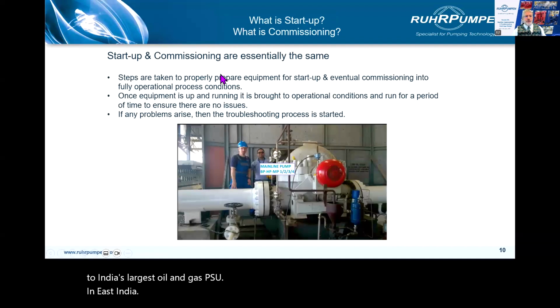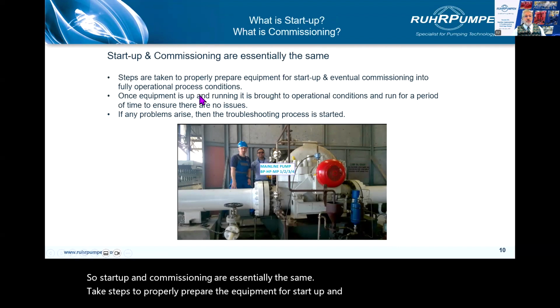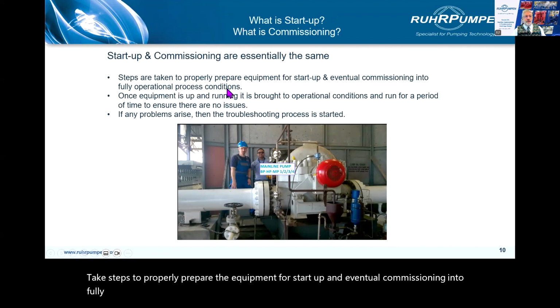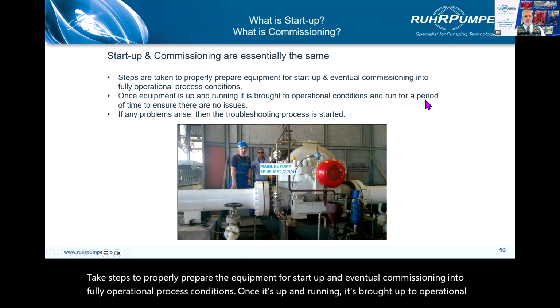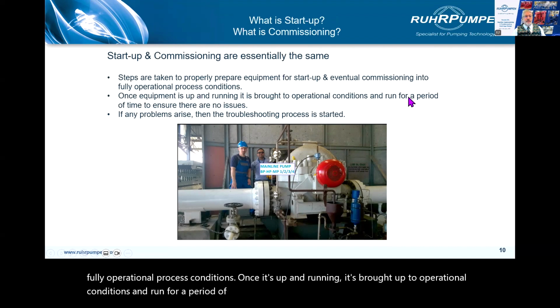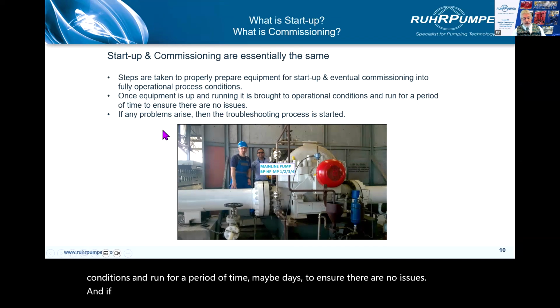So startup and commissioning are essentially the same. It takes steps to properly prepare the equipment for startup and eventual commissioning into fully operational process conditions. Once it's up and running, it's brought up to operational conditions and run for a period of time, maybe days, to ensure there are no issues. And if any problems do arise, then we start the troubleshooting process.